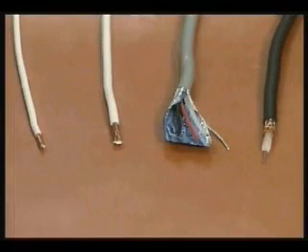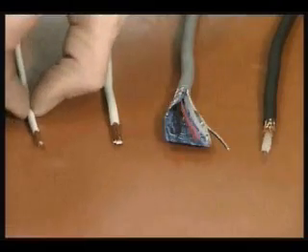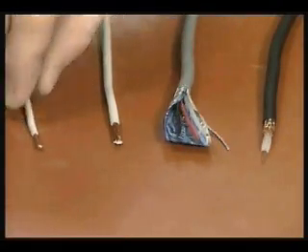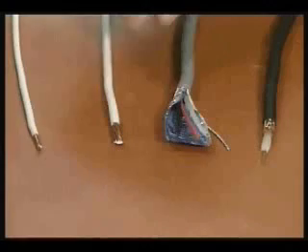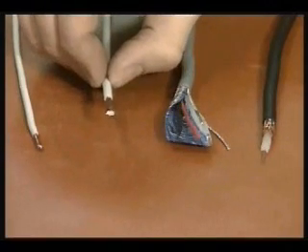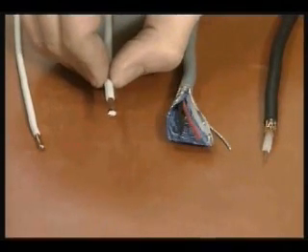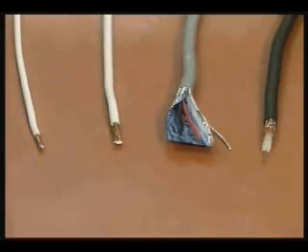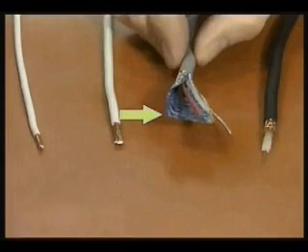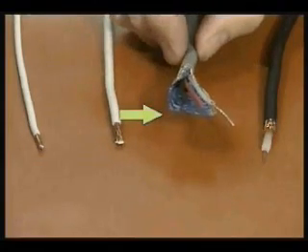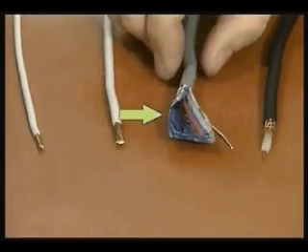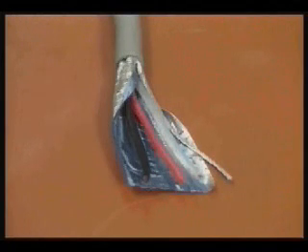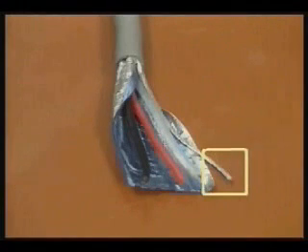You may be familiar with types of industrial wires and conductors. Solid conductor wires are solid metal, usually copper, covered by insulation. Stranded conductor wires are strands of metal twisted together and covered by insulation; these wires are more flexible than solid conductors. Shielded cable has a metal shield between the insulated conductors and outer jacket. The shields can be braided metal, stranded metal, or foil. A foil shield may have a drain wire to permit easy connections to ground.